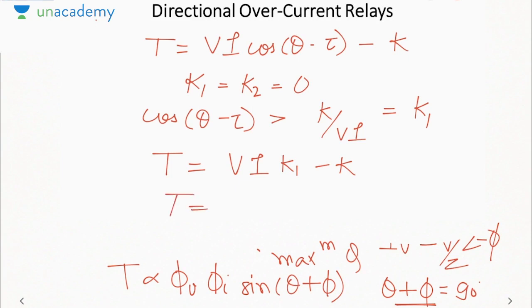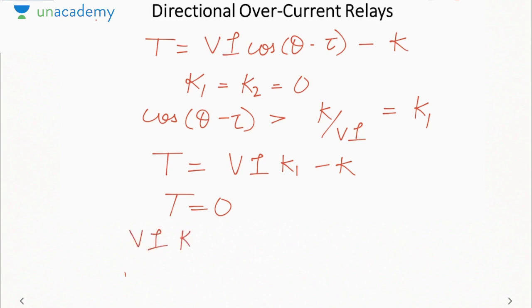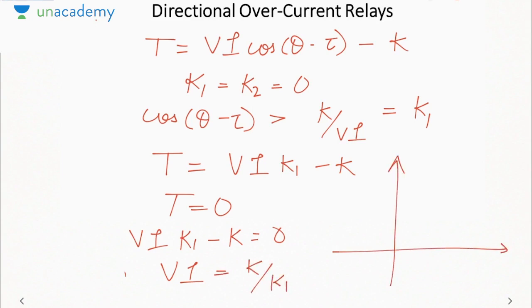Now when torque is 0, what will we say? The boundary condition is when torque is 0, then V i into k1 minus k is equal to 0, so V i is equal to k by k1. So the characteristic on the V i plane will be hyperbolic. It will be like this. Why have I taken minimum values of current and voltage? Because it is an overcurrent type of relay, so below a certain value it will not operate. Hence there will be some minimum value of current and some minimum value of voltage.